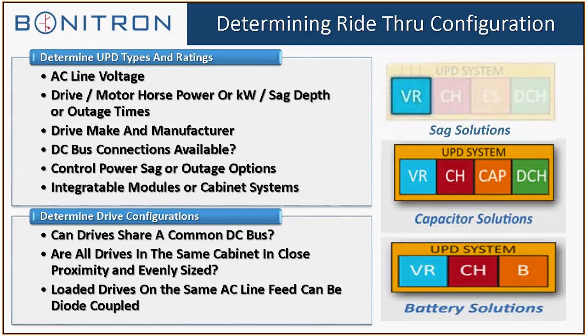Of course, we need to know the AC line voltage, because the DC is directly proportional to the AC line voltage, so it's going to vary. US is always 480. For instance, Canada is 575. So the DC bus is going to have different threshold levels where the ride-through turns on in relation to what the AC line is.